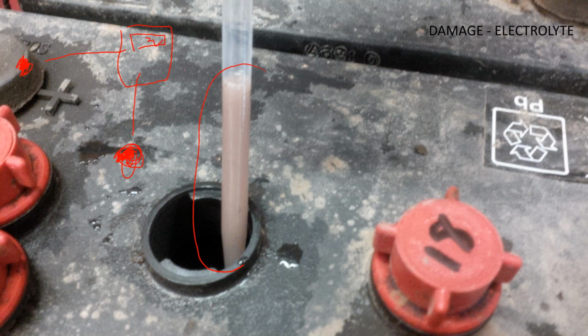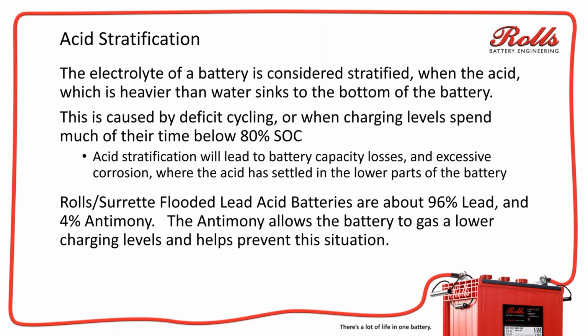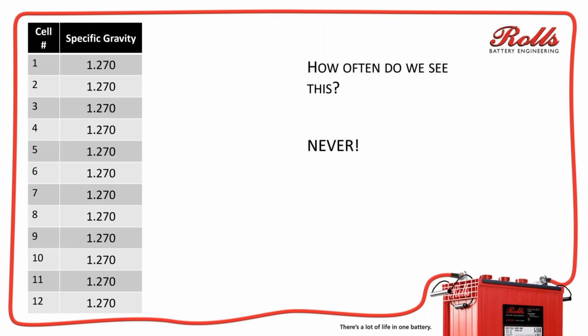And the only reason there's voltage there is because there's been electrolyte spillage on the top of the battery. So whenever I go to a battery site, I'll take my voltmeter and measure this, especially if I see the tops of batteries that look a little dark. That will tell me that there's definitely been spillage on the battery in the past.